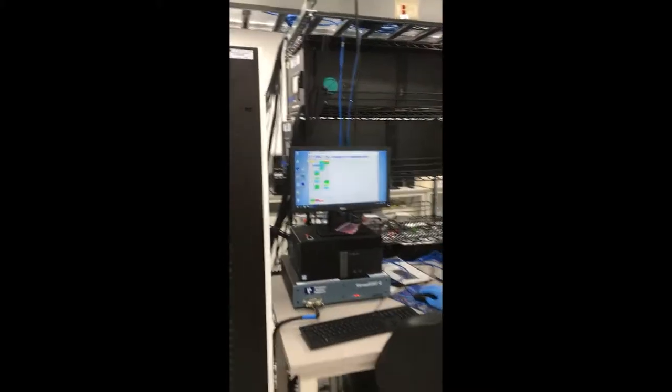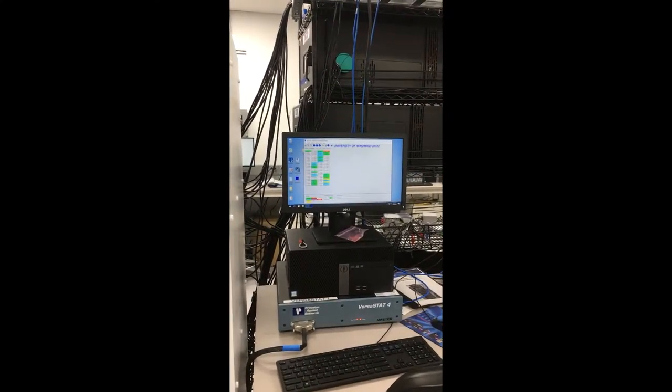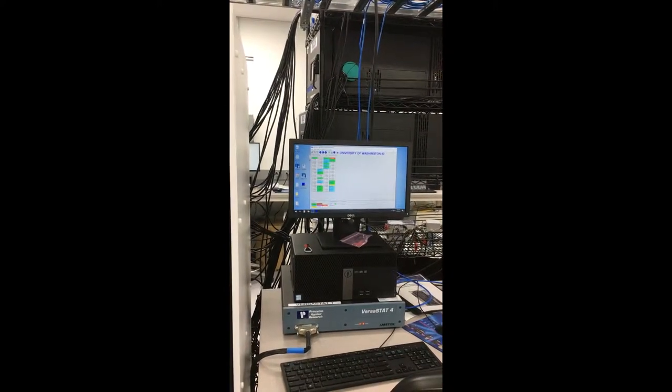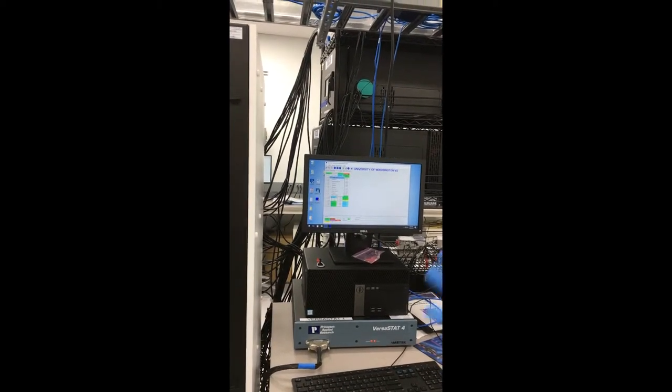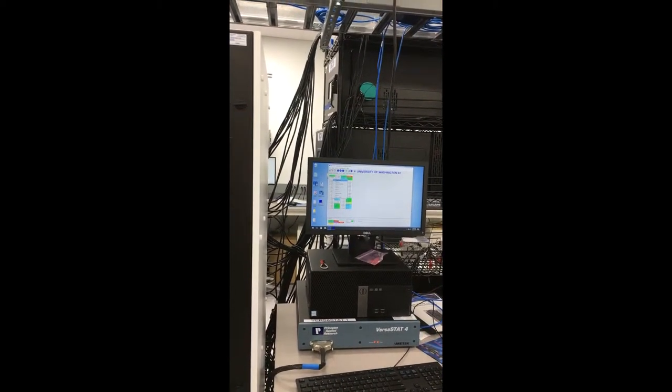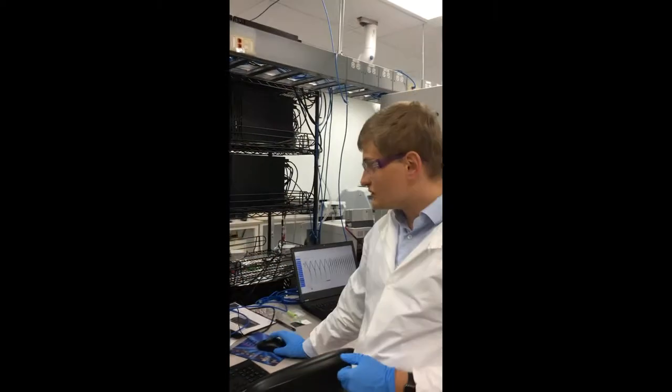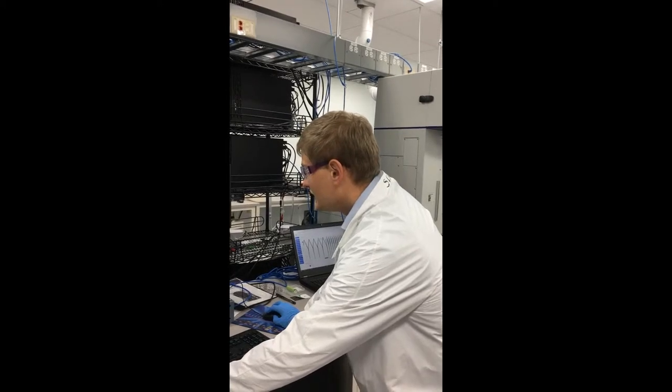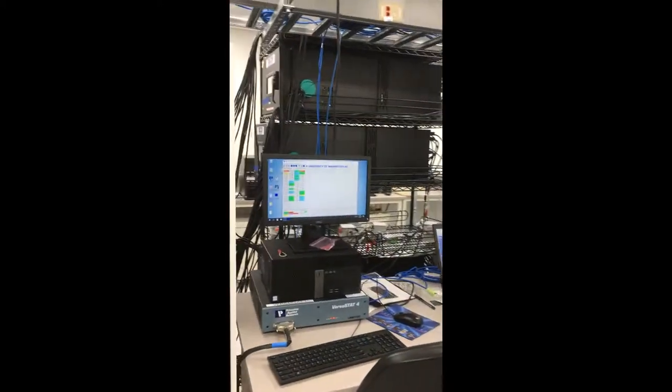Same I will do with third channel. This is a bigger battery. And I will also start another test of it. But what exactly are you measuring? So right now, we are going to charge and discharge it to specific voltage and specific current. And we are trying to understand how long this battery is going to last. We are scheduling something right now. And this will start. On this machine to do a certain thing. Yeah. Test scenario.